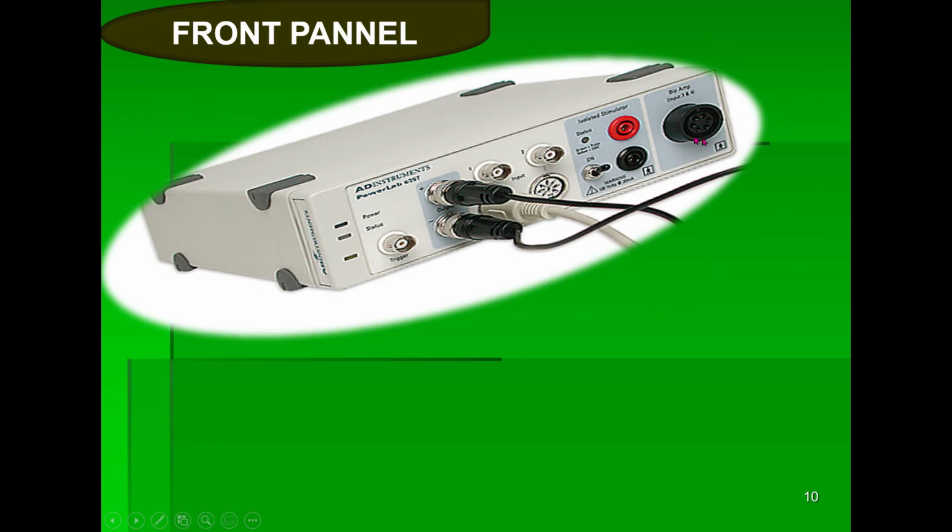Here you understand that this black one is the input connector, meaning it can acquire data from outside to inside, from the human body. This blue part is for the human subject, and this part is for the animal subject. So first of all, we will study the human subject. This bioamplifier knob is a knob to which we attach the bioamplifier cable, so that we can input the data. For example, ECG, EMG, nerve conduction signals, all these signals can be input into the Power Lab with the help of this bioamplifier cable.